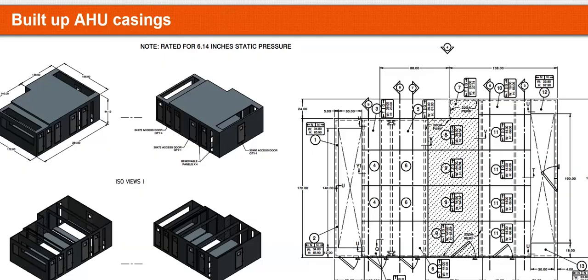In this specific case, this is a top secret facility in Denver for a government building. You can see the panel layout. You can see that the fan room sections have perforated liner inside. Why? Because you're trying to attenuate sound right at the source. The main source within an air handling unit is obviously your return fans or your supply fans. So adding perforated metal there will result in a quieter discharge sound power level of the unit. The rest of the assembly is a solid construction. You're trying to block, maintain temperature, but also in the coil section, if you experience condensation internally, you don't want to have that perforated metal exposed over a long period of time.